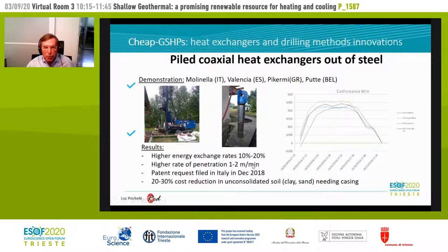The penetration rate is also quite high because we are piling. The installation rate is high because we don't need to do a casing to support the borehole, since the external tube of the heat exchanger keeps that borehole open -- especially useful in soils, for instance in northern Italy, where boreholes collapse.